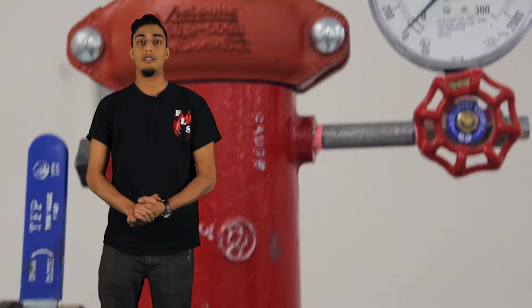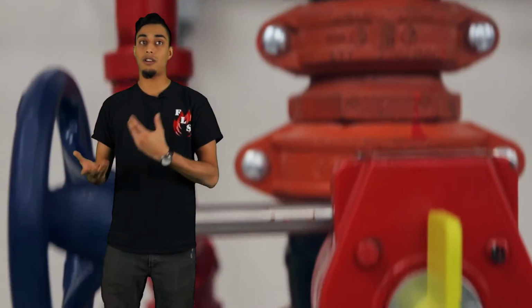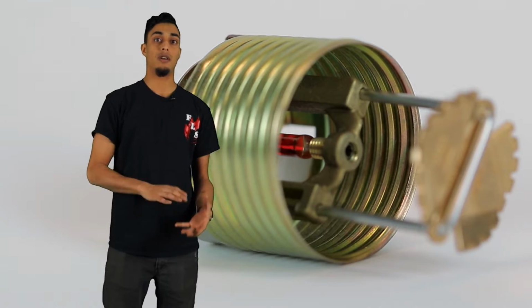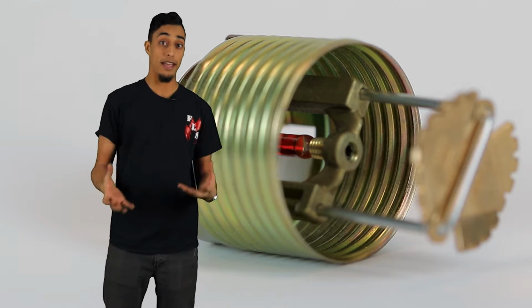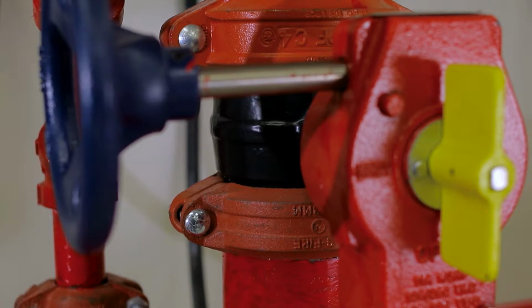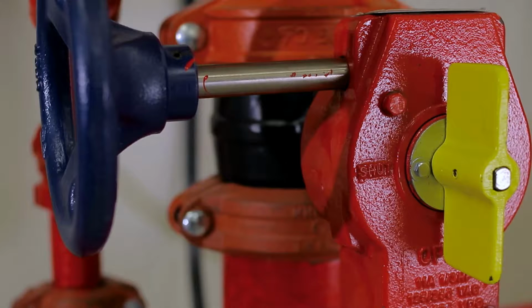Part 2. Testing a tamper switch. Tamper switches are electrical components installed in our sprinkler system to ensure that everything is functioning the way it should. The most common location you'd find a tamper switch is in the main control shutoff valve. And this is to determine whether or not the valve has been tampered with or closed up to about 20%. This is defined explicitly in NFPA 25.